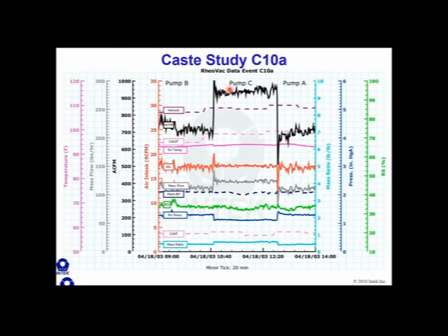So if you have your data slide, you can pull that out, and then you can also look at the validation parameters from the handouts, the table. So here's pump B, pump C, pump A. I'd like you to use that troubleshooting flow chart. What's the first question we should ask? It's, is the water to air mass ratio less than 3? It's in teal. Yep, it's less than 3.